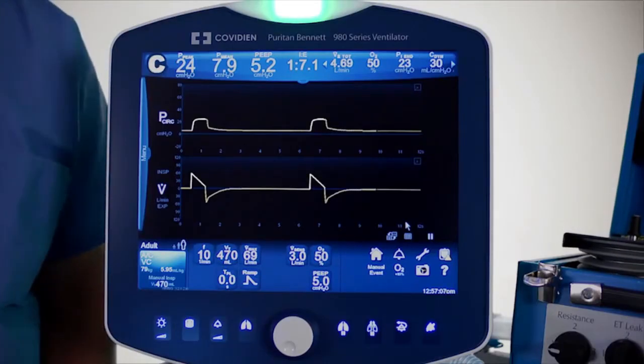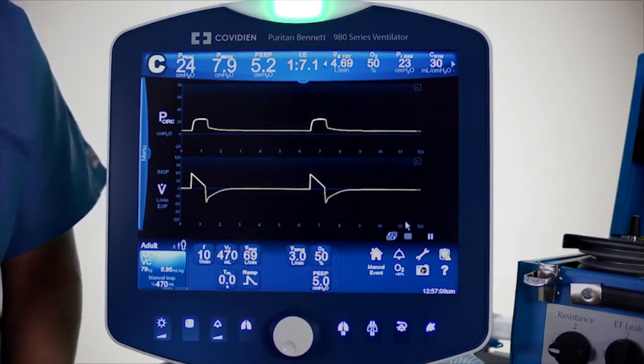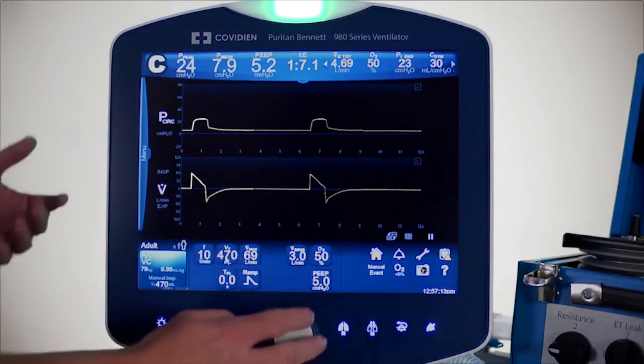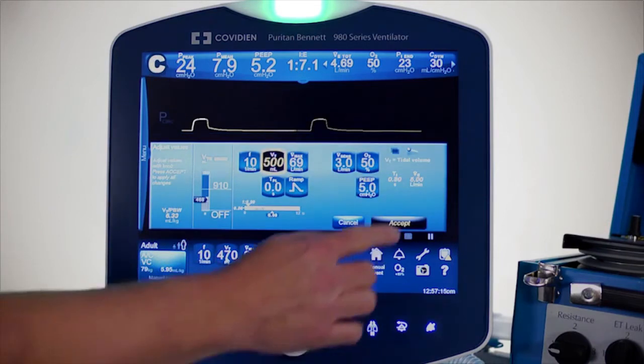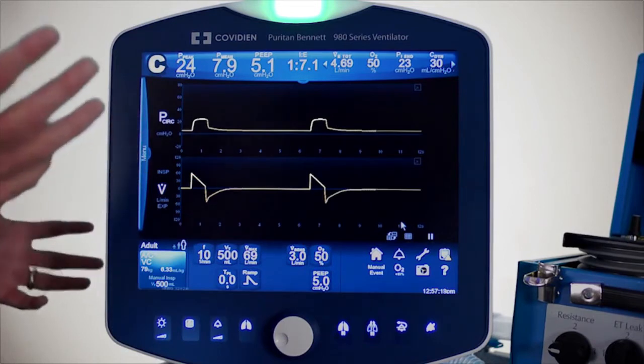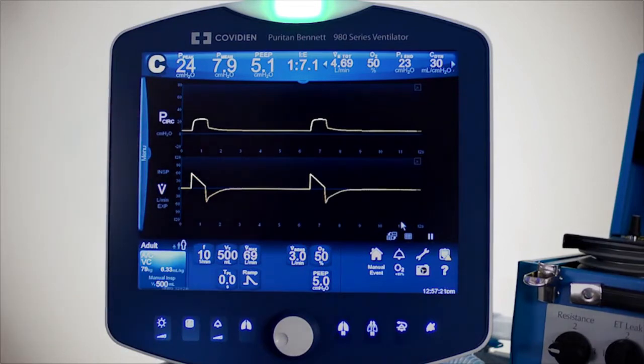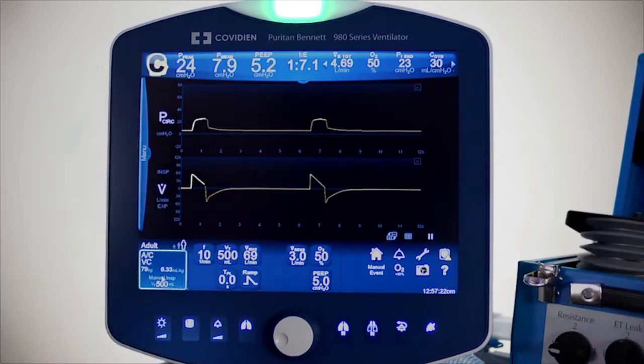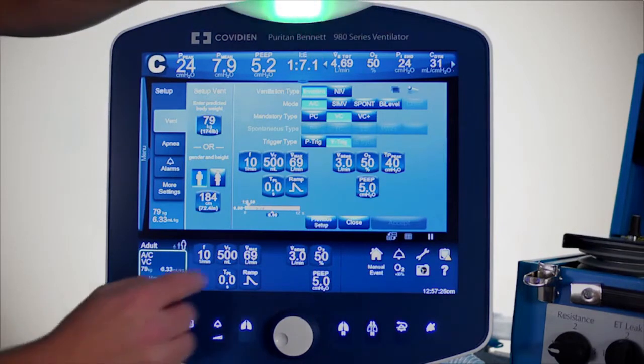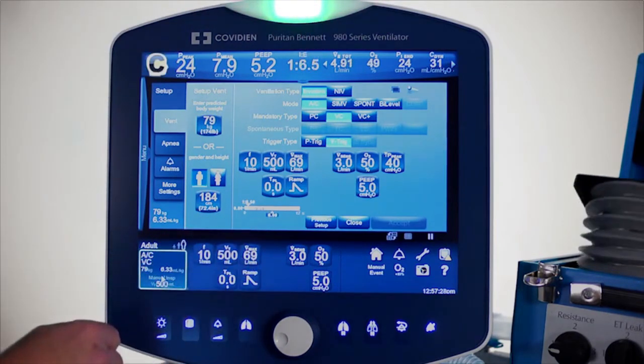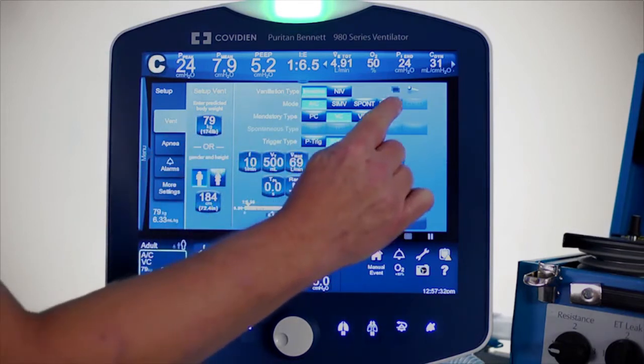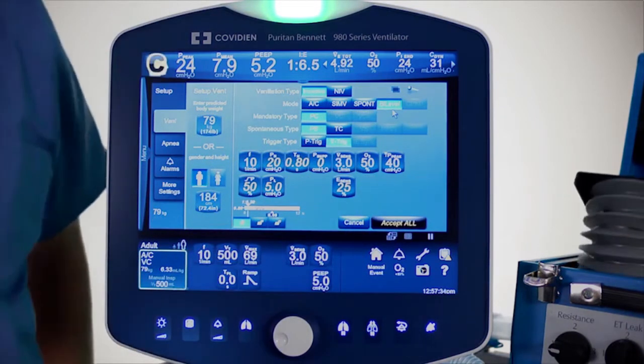Currently starting in volume control ventilation. If someone was converting over, they may look and say their target was 500 milliliters and want to see if that's where they want their patient to be. Starting under the Vent Setup button, bi-level works from neonates to adults but only works invasively. I'm going to select bi-level as a mode.